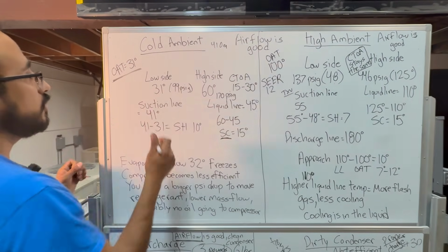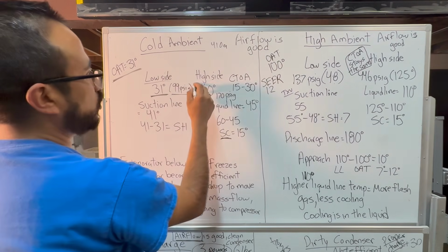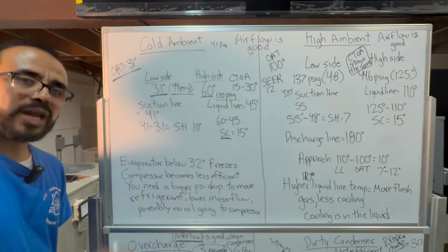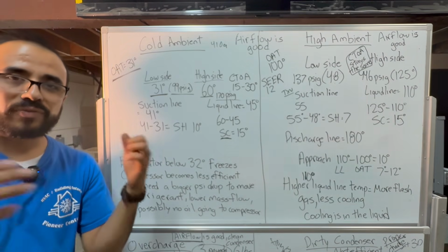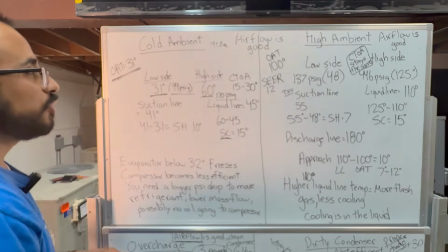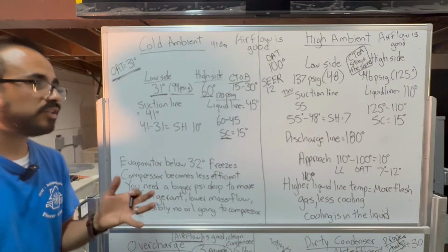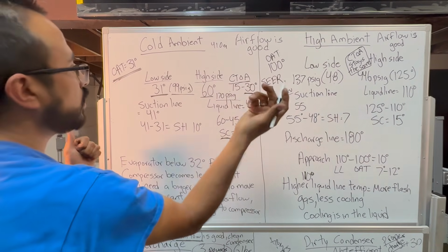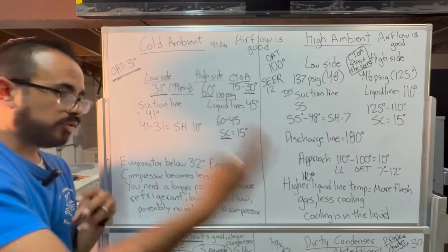System turns on. And so my low side pressure is 99 psi, evaporator temperature of 31. My high side pressure is 170 psi. I have a condensing temperature of 60. So it kind of makes sense. In this specific case, of course, I wasn't able to do it here in a controlled environment because I couldn't get to 31 degrees here. But the principles still apply. So remember, condensing temperature over ambient varies depending on what SEER it is, right? 15 through 30, more or less. But in this case, I chose close to 30. So if my ambient temperature is 31, add 30 to that, right?